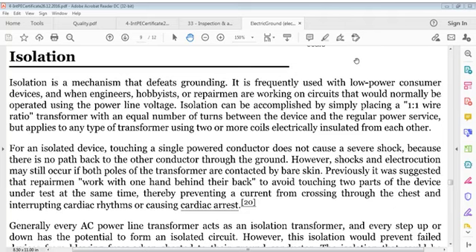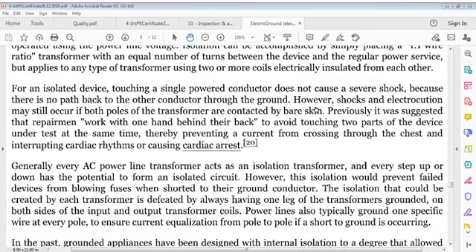1:1 wire ratio transformer with an equal number of turns between device and regular power service, but it applies to whatever type of transformer using 2 or more coils electrically insulated from each other. For an isolated device, touching a single powered conductor does not cause a severe shock because there is no path back to the other conductor through ground. However, shocks and electrocution may still occur if both poles of the transformer are contacted by bare skin.